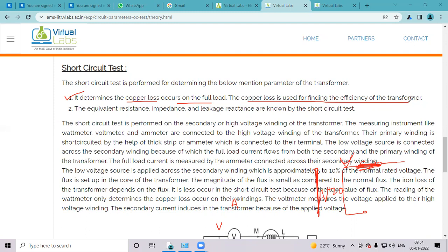Once the losses are known, we are able to calculate the efficiency. So after that we are finding the efficiency of the transformer. Also, the second parameter, which is also determined by performing the SC test, is the equivalent resistance, that is R01 or R02, depending on which side it is referred to. Then the impedance, that is Z01, and the leakage reactance, that is X01. X01, R01 and Z01 when referred to the primary.